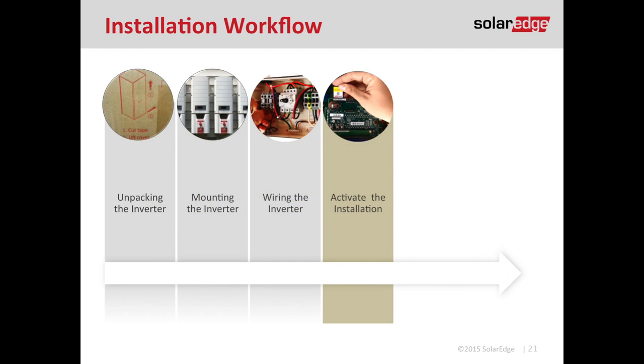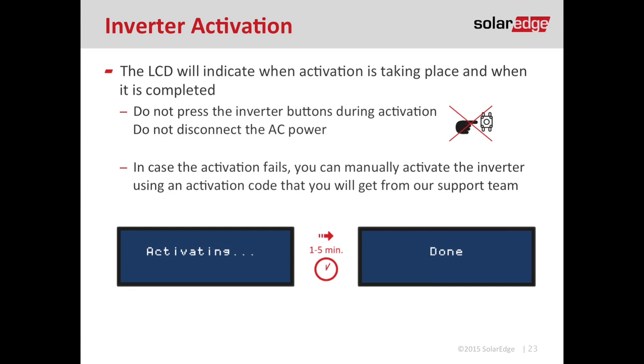After you've landed all your conductors, we're at step four of the installation process: activating the installation. Take the brown box we pulled out of the viewing window earlier — inside there's an envelope with an SD card that looks like a micro SD card. Insert that SD card into the top of the communication board where a sticker identifies the SD card slot. Once the card is inserted, turn on AC power to the site. The inverter will automatically sense the card and start the activation process, which takes about one to five minutes. Don't turn off the inverter during this process.